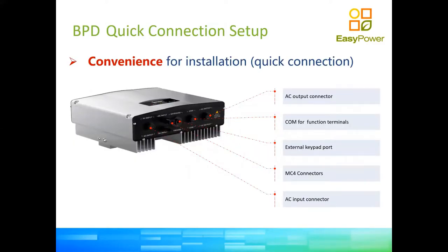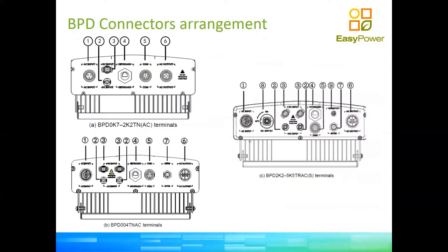The 4 kilowatt and 5.5 kilowatt BPD models come with 2 MPPT inputs, which is great if, for example, you have panels on a northwest-facing roof and others on the east — you can separate the two arrays to maximize power production from both orientations throughout the day. The smaller models of 2.5 kilowatts and below have only one MPPT input. All models have a keyboard port connection and a COM communications connection — RS-485 — that allows you to connect to a computer using a standard plug with three wires.